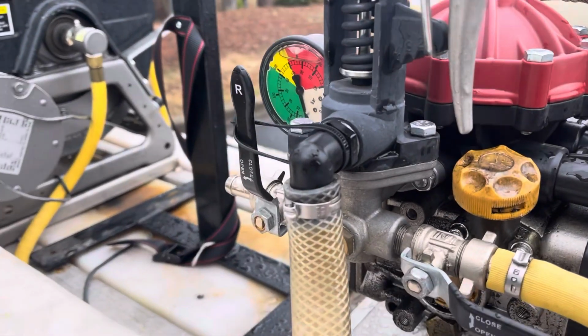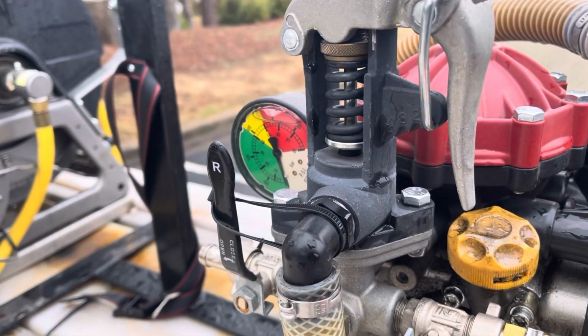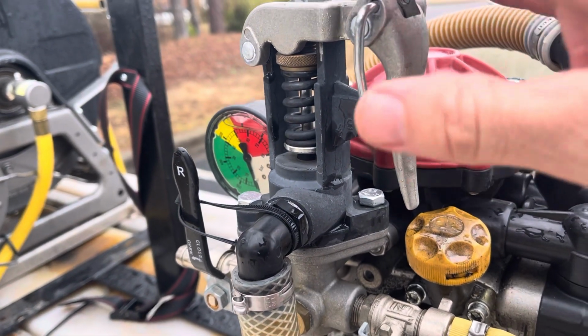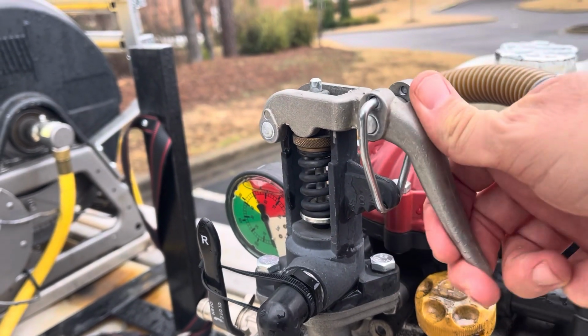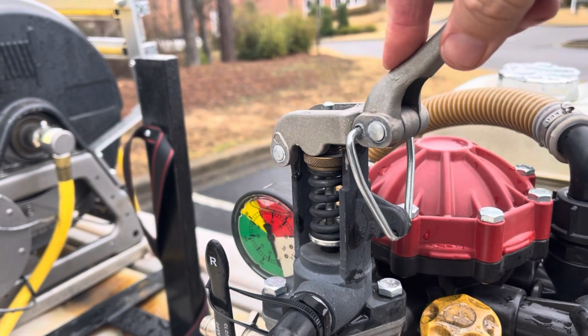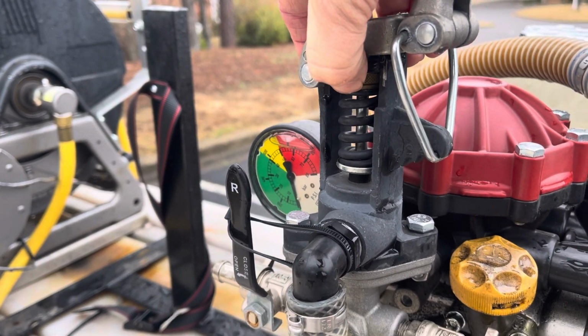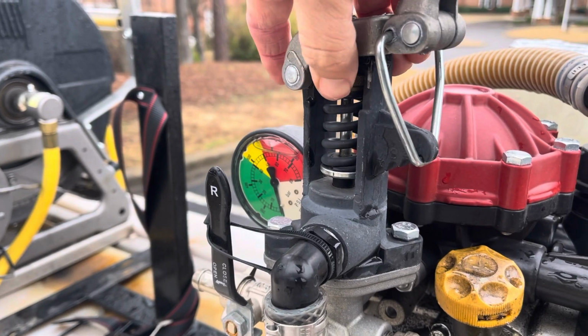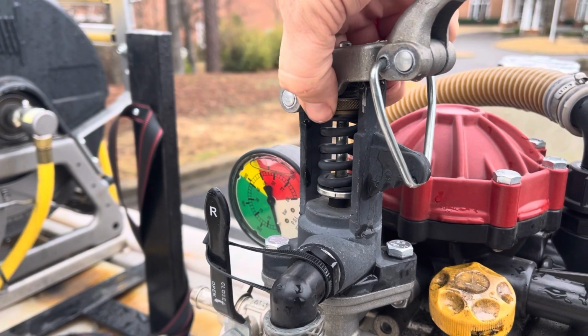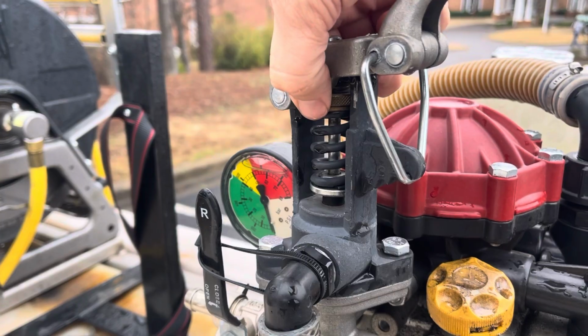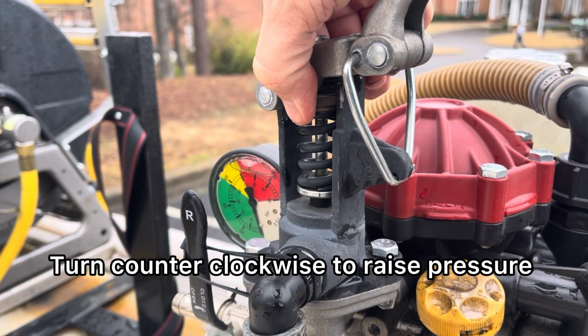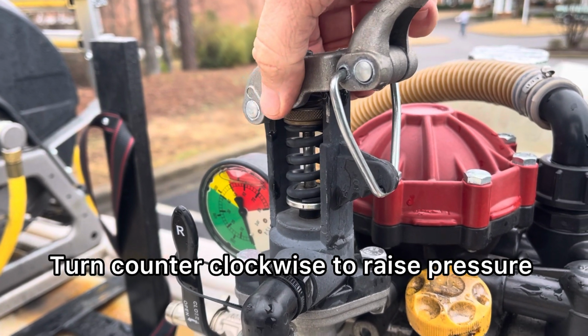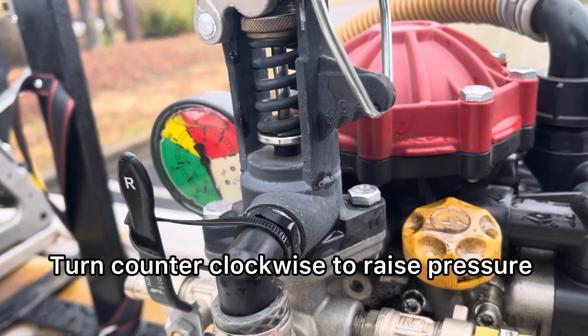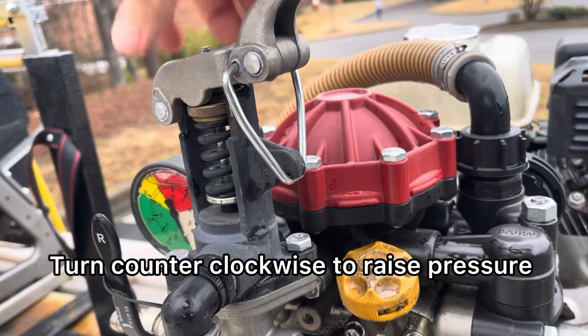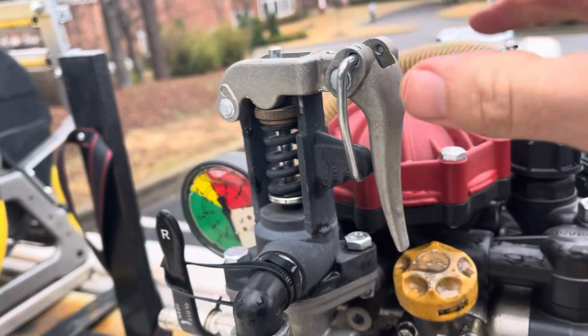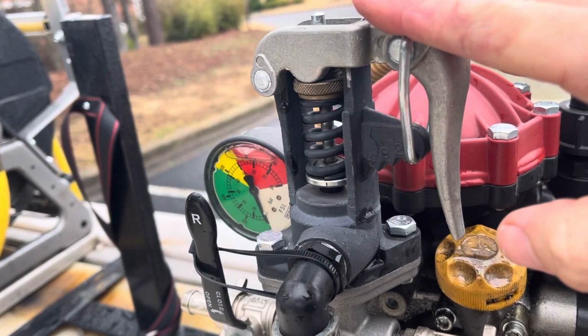Here's my pressure regulator. I've cut the pump off just so you can hear me talking, but you can actually do this while the pump is running. You lift up on this, there's a little knob here, and you turn it - I always have to play with it, I can never remember - I think you turn it to the left to raise your pressure or turn it to the right to lower your pressure. It could be the opposite way. So I'm going to play with that for a minute, and once you got it where you want, you close that back down, and that locks the pressure back in.